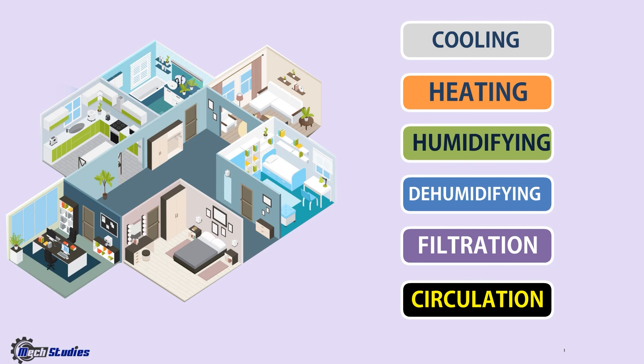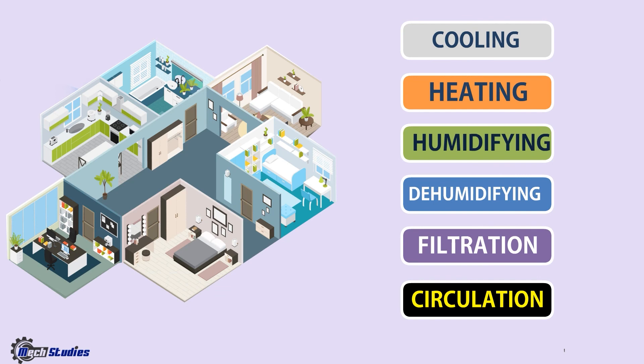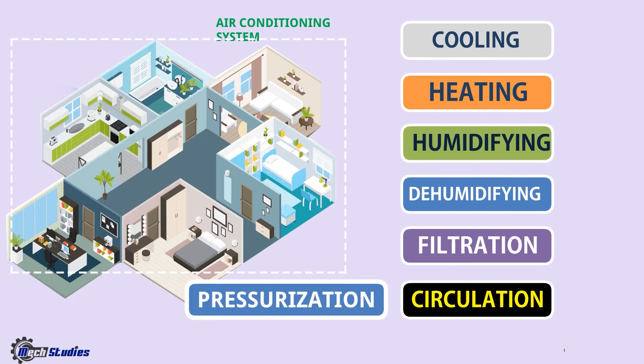Pressurization - the outside atmosphere contains dust particles and other foreign particles. If we slightly overpressurize our buildings or conditioned areas, outside dust particles will not infiltrate the building. So slightly overpressurizing will help protect the building from dust particles. This pressurization process can also be done by the air conditioning system.